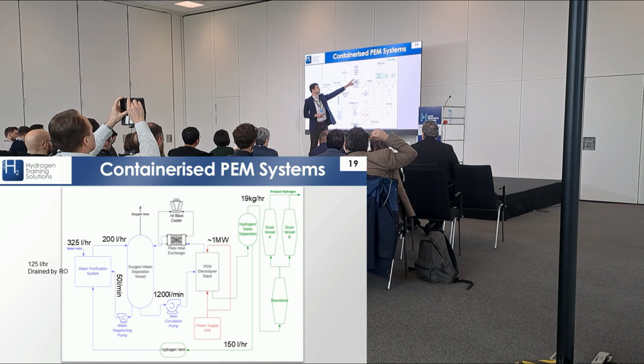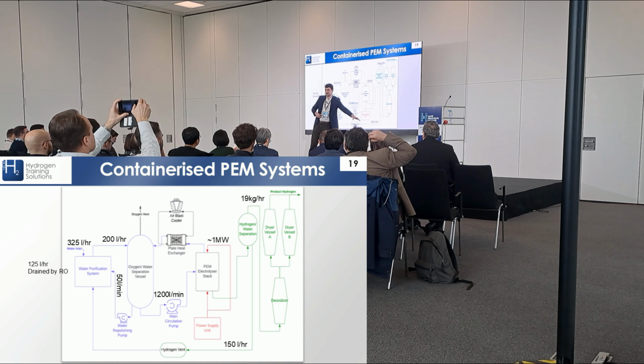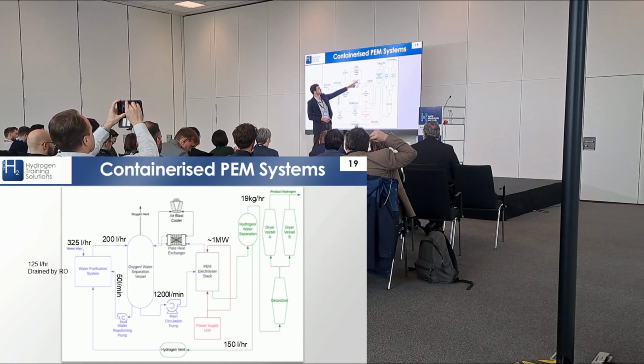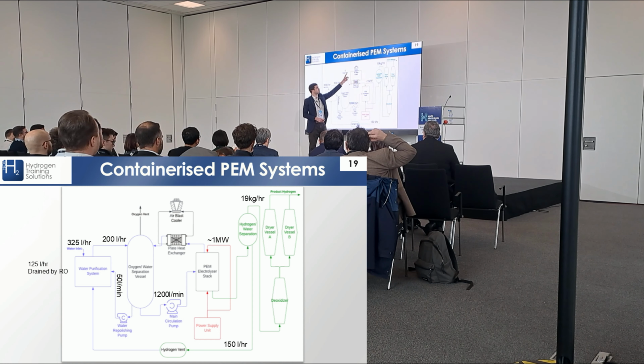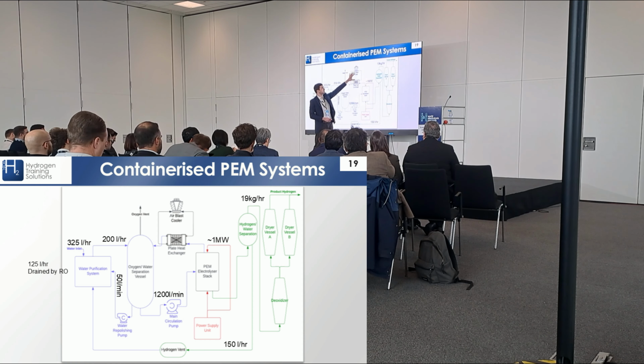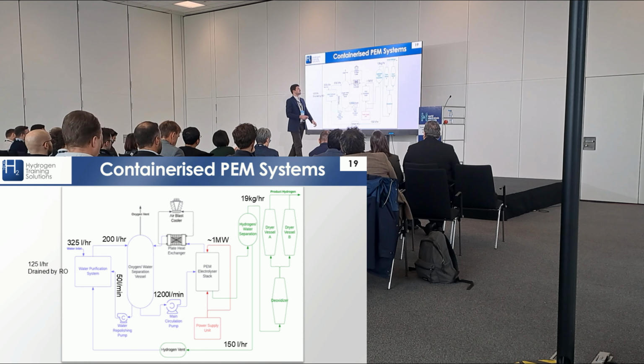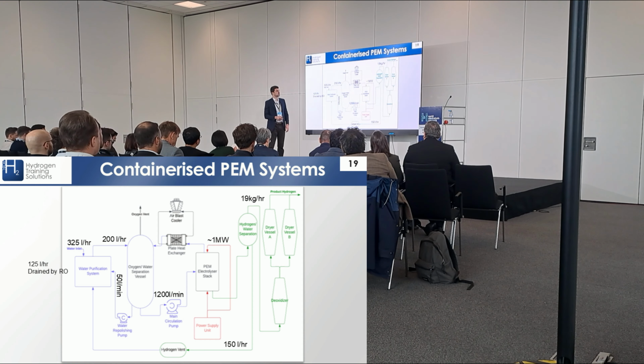The plate heat exchanger provides cooling, but it's located inside, because we don't want the water going outside, as in winter it would freeze. So we use a different medium - some sort of coolant with an inhibitor inside - which goes outside into the air blast cooler to provide the cooling.